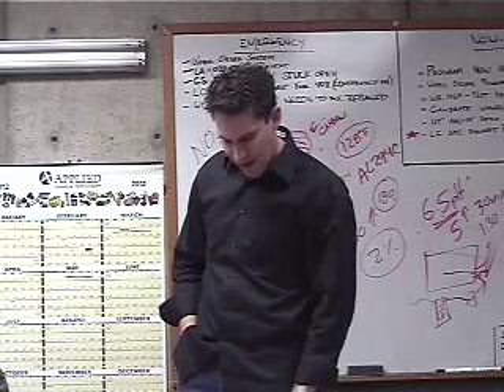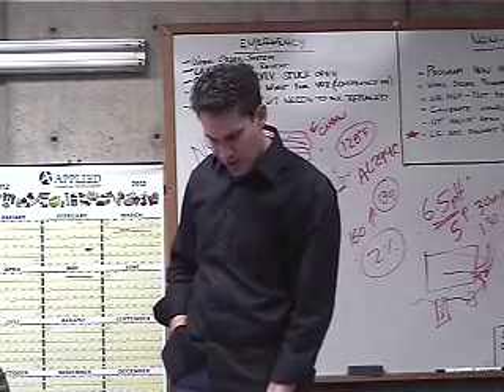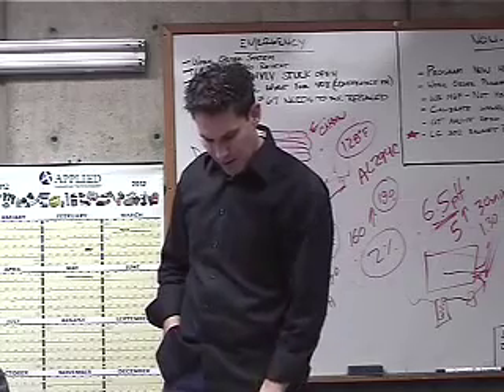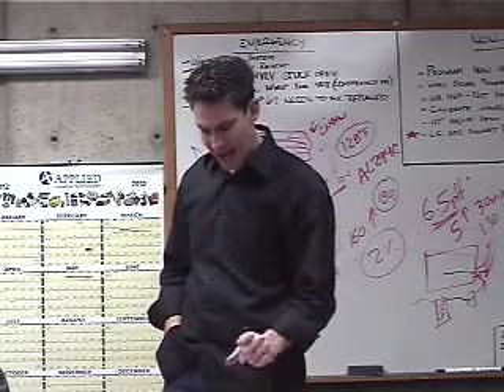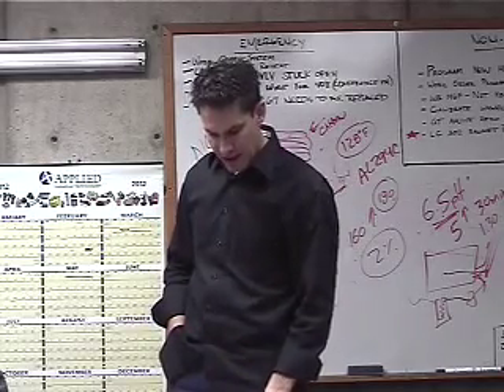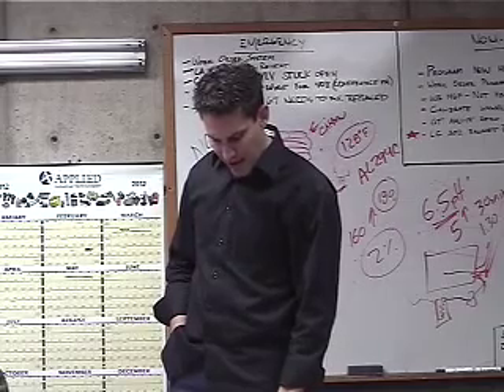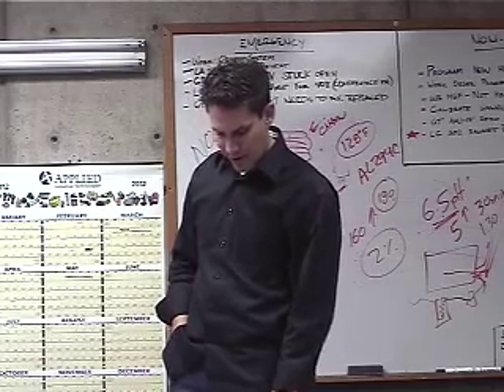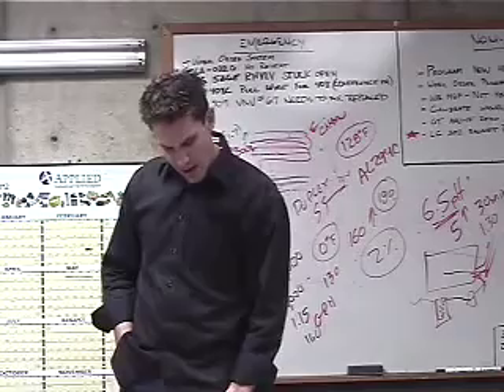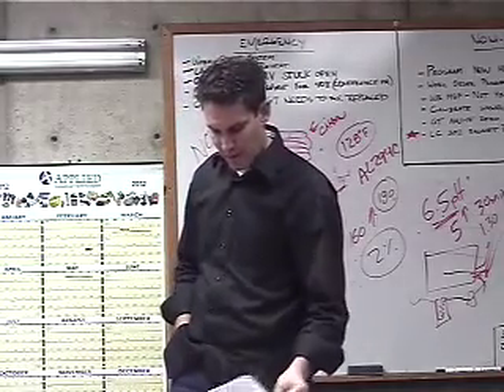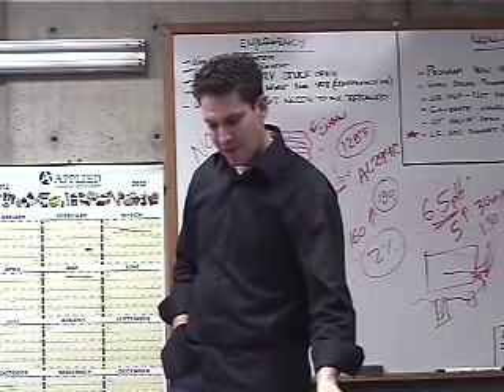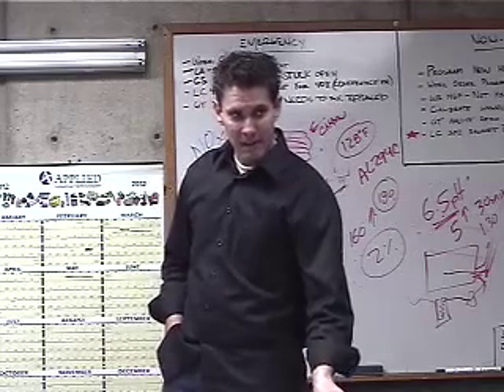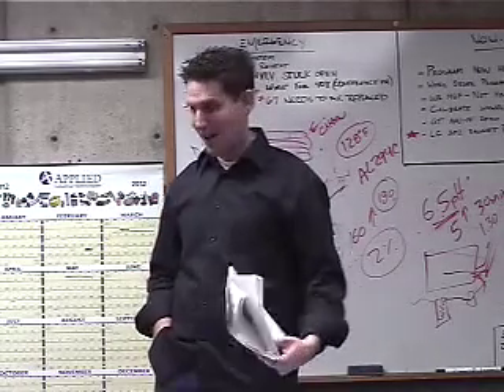Inspect the hydronic heating system for other problems, perform combustion analysis. Okay, so that's what we're talking about here. Perform combustion analysis and adjust it if necessary. Leak test all of your gas valves and test your pressure relief valve per the manufacturer's instructions, and they tell you how to do that. For 5 seconds, lift the valve and allow it to snap shut. Pretty simple, right? You guys nervous? Have I scared you a little bit?